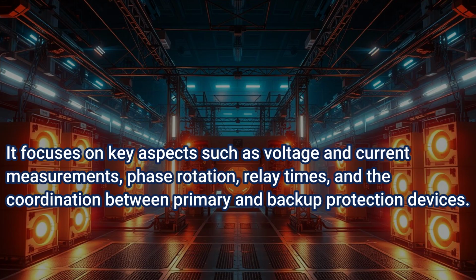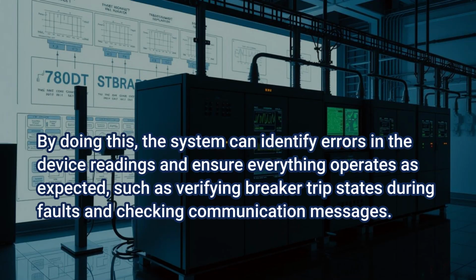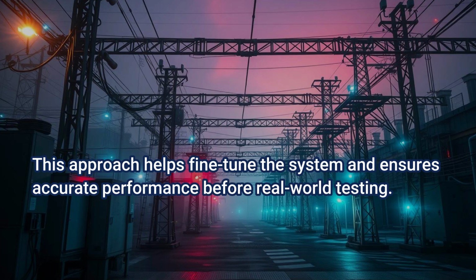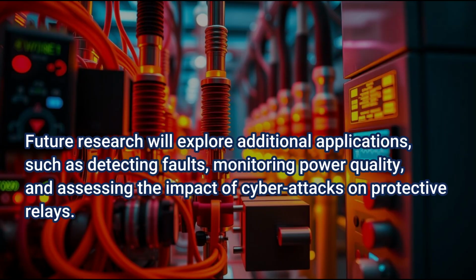and backup protection devices. By doing this, the system can identify errors in the device readings and ensure everything operates as expected, such as verifying breaker trip states during faults and checking communication messages. This approach helps fine-tune the system and ensures accurate performance before real-world testing. Future research will explore additional applications, such as detecting faults, monitoring power quality, and assessing the impact of cyber attacks on protective relays.